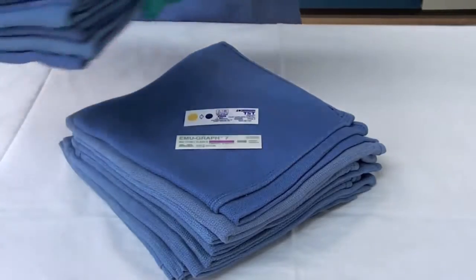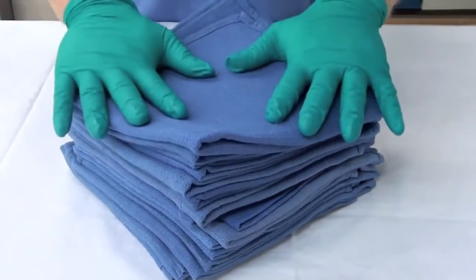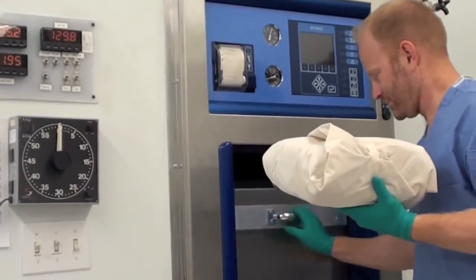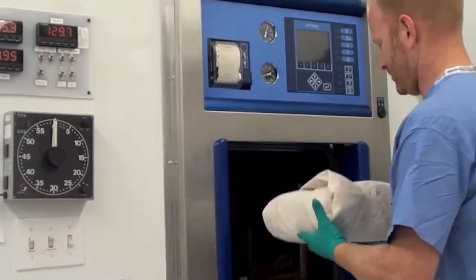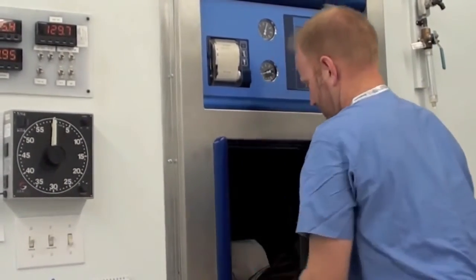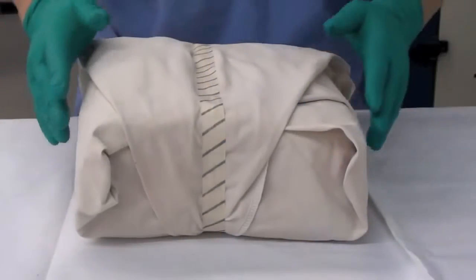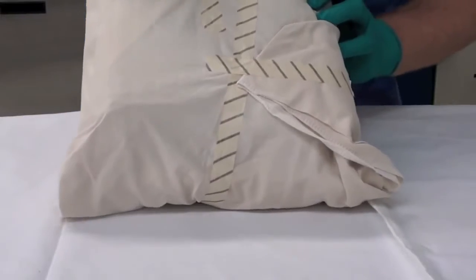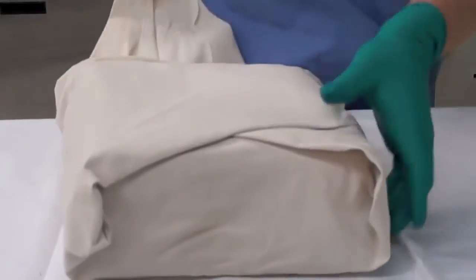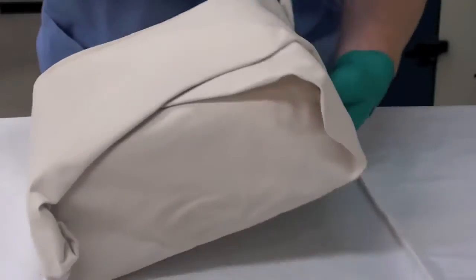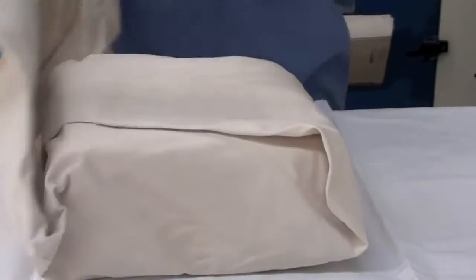We place both of these indicators in a simulated failed cycle with an exposure time of 4 minutes following the air removal phase of the cycle, which is only 57% of a full cycle for these indicators. The result should clearly indicate that the cycle was incomplete by demonstrating a fail result with yellow or purple color still present. After ending the cycle, we unwrap the towel pack and examine the results.